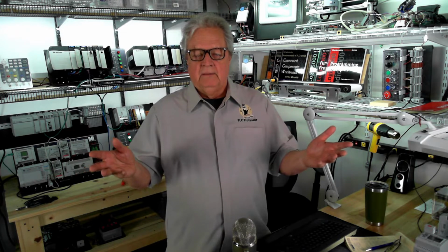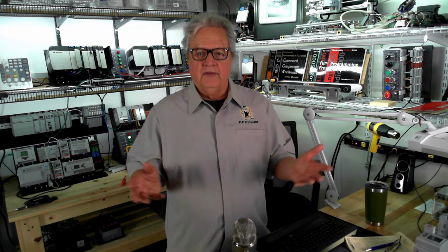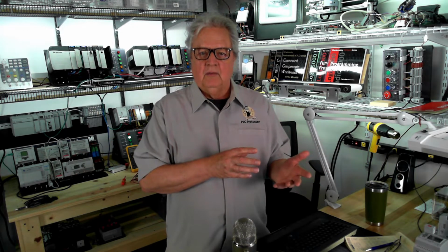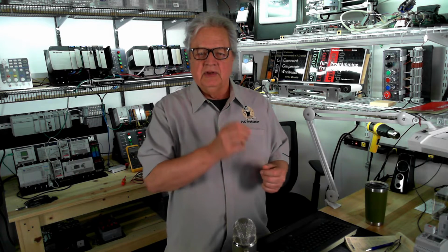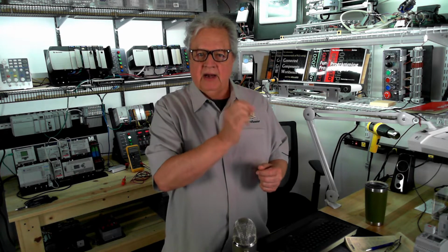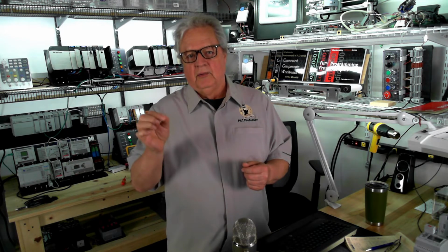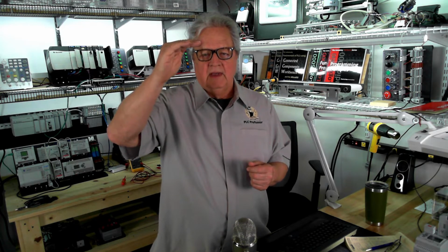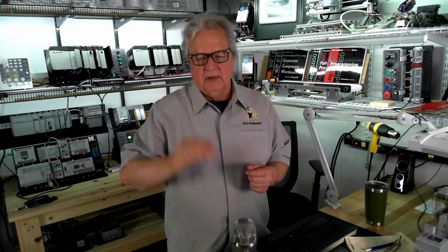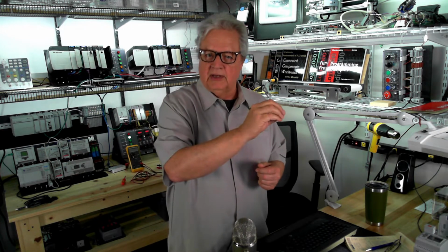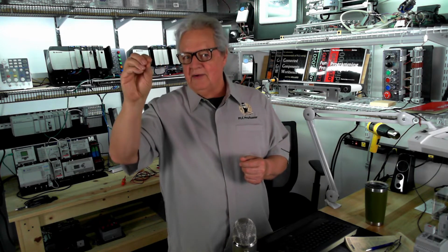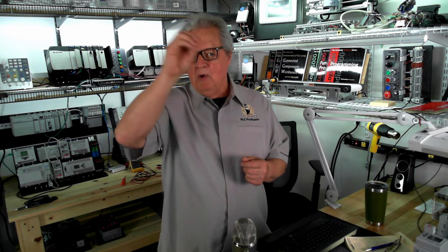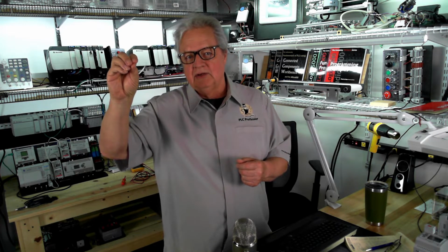And basically what we're doing is we're taking all the embedded I/O and we're rung by rung copying the state of that embedded I/O module-defined data type bit into a global variable data bit that we created. And we do it at the beginning of the program. And then when we're running the program, instead of using the embedded I/O bits, we use the other bits that we move the embedded I/O state into.